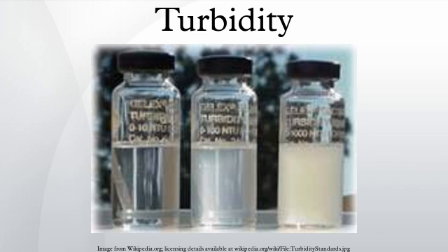In situ treatment of turbidity involves the addition of a reagent, generally a flocculant, evenly dispensed over the surface of the body of water. The flocs then settle at the bottom of the water body, where they remain or are removed when the water body is drained. This method is commonly used at coal mines and coal loading facilities where stormwater collection ponds have seasonal issues with turbidity. A number of companies offer portable treatment systems for in situ water treatment or direct dosing of reagents.